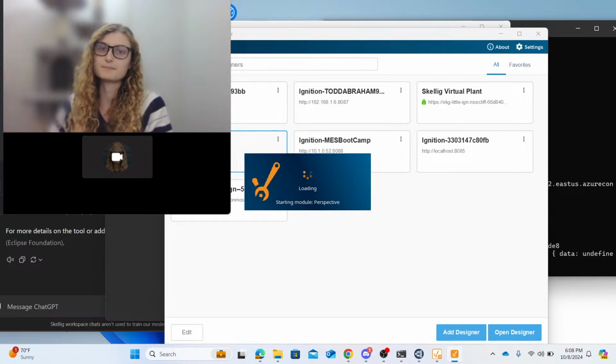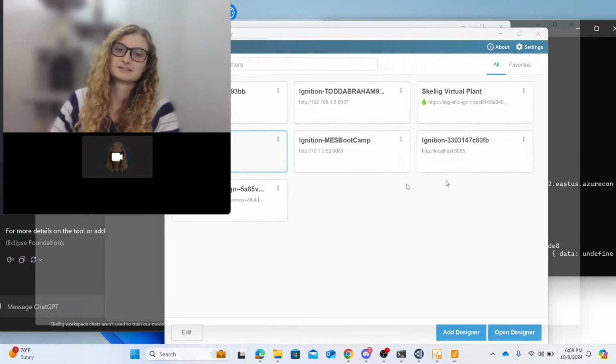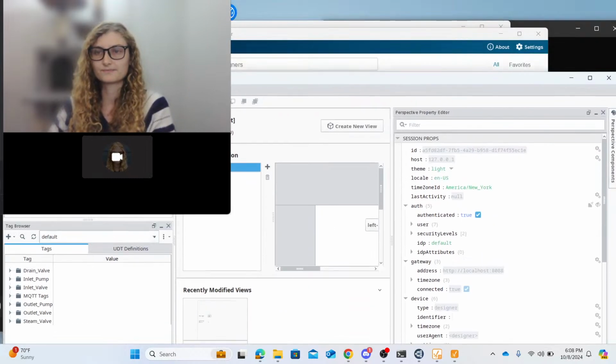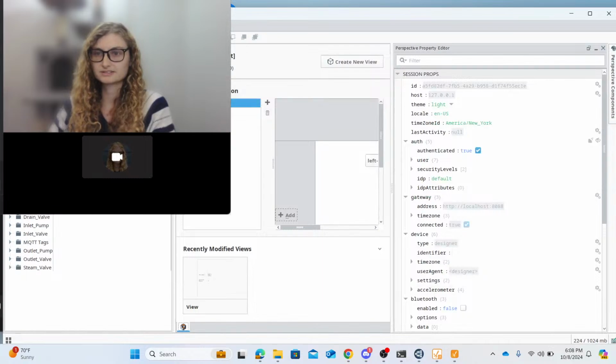So what I'm hoping to see in this broker here is first the node birth message followed by the device birth message. Then when we write to a set point, I'm hoping to see a D command message with the new set point value going. Then when that value changes, I'm expecting to see a D data get published back. So hopefully we'll see all four messages easily in this little broker. All right, so let's go. Hopefully we're sharing the right screen.